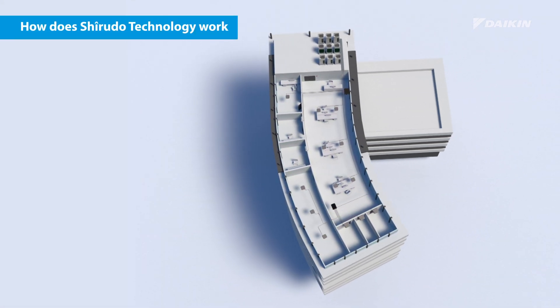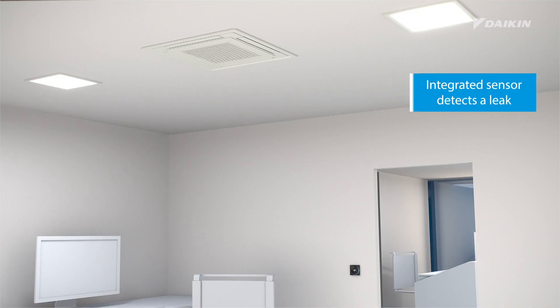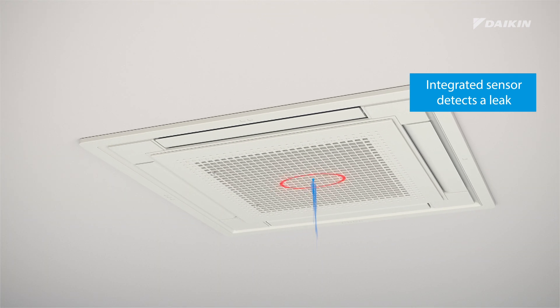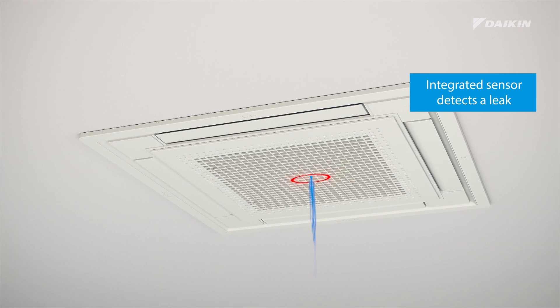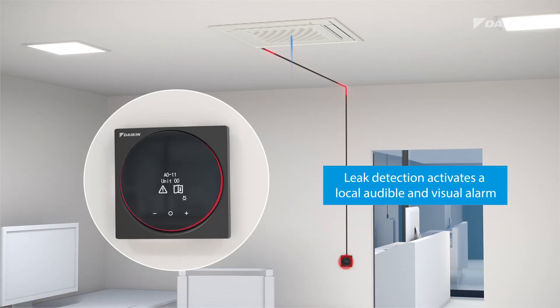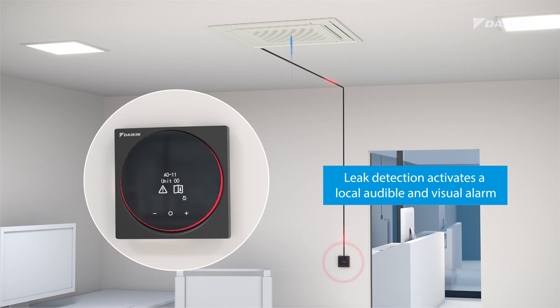How does Shirudo Technology work? In the unlikely event of a refrigerant leak, the integrated sensors in the indoor unit will immediately detect it. The leak detection sensor then activates a local audible and visual alarm integrated in the Madoka controller.